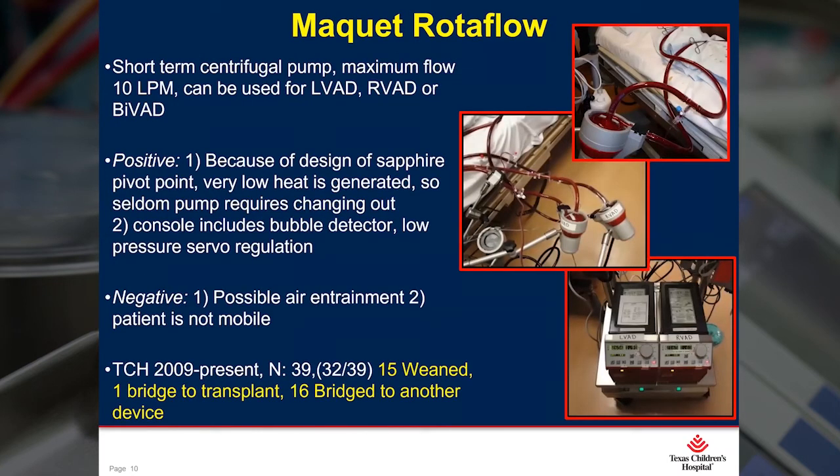The next pump we introduced was the Maquet Rotaflow centrifugal pump. This is also a short-term device and it replaced the Medtronic Biomedicus. It has a much improved design with very little heat generated on the backside of the pump, so we rarely have to change out one of these pumps while they're in use. The console also includes safety features such as a bubble detector and low pressure servo regulation. The negative, like all short-term VADs, is that there is a chance of possible air entrainment and the patient does have to stay immobile. We started using the Rotaflow in 2009 and have inserted a total of 39 patients as VADs — 15 have weaned, one transplanted, and 16 bridged to another device.